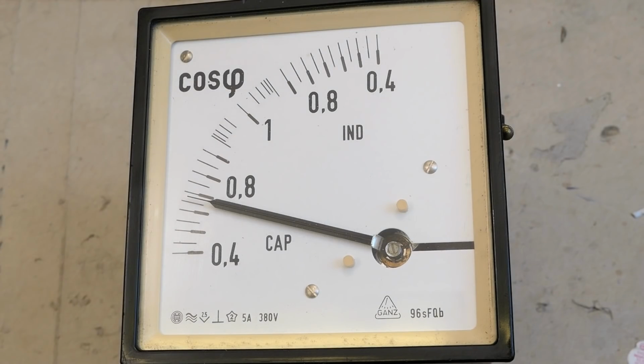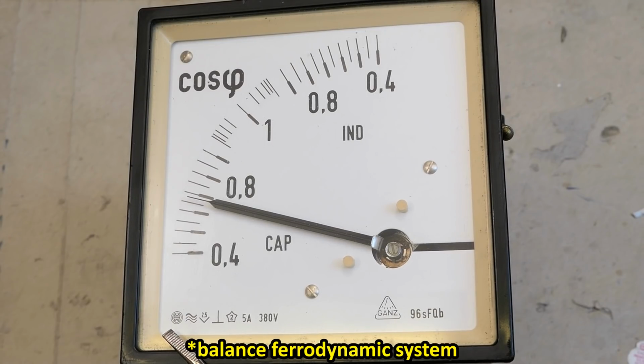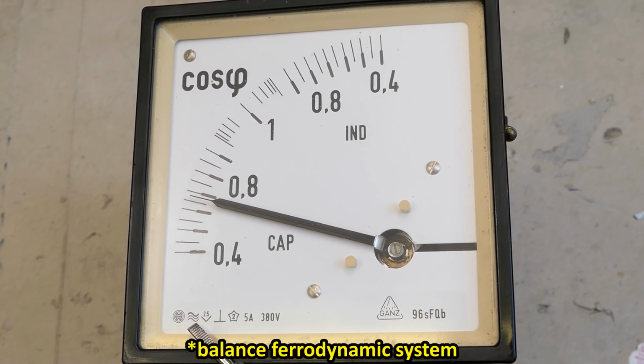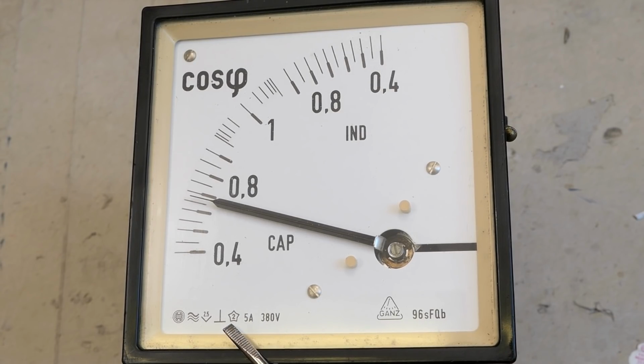But now let's start exploring the internals. Let's begin with this one. The system is again ferrodynamic, 3 phases but current sensing in one phase, 2.5% accuracy, vertical operation, 2 kV test voltage. The current sensing coil is rated for 5 amps and 380 volts for the voltage coils or reference coils.